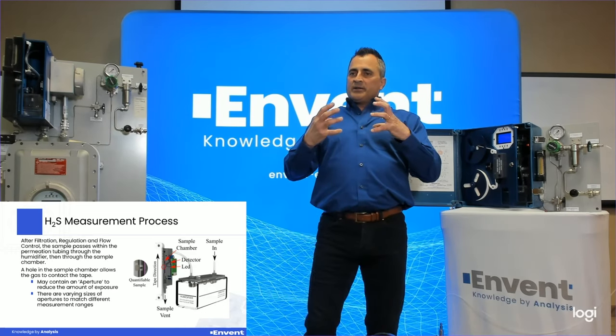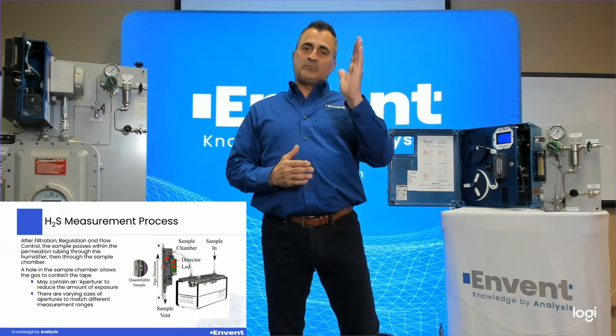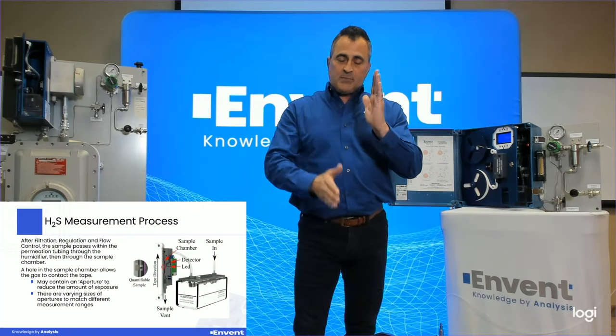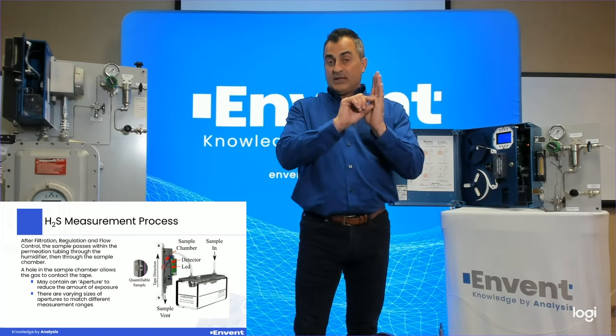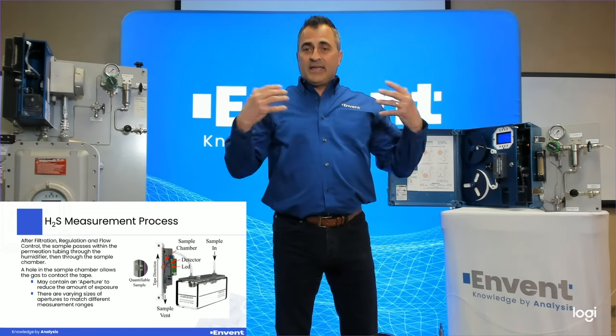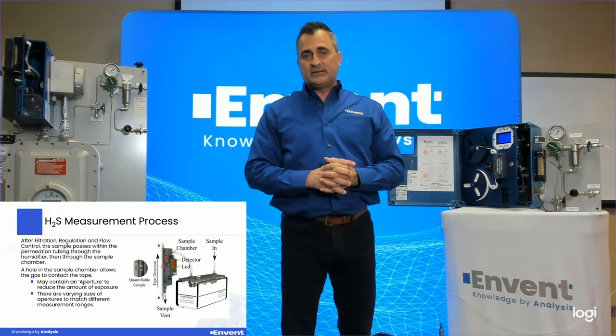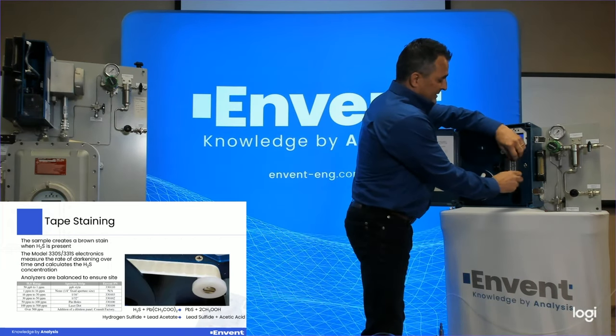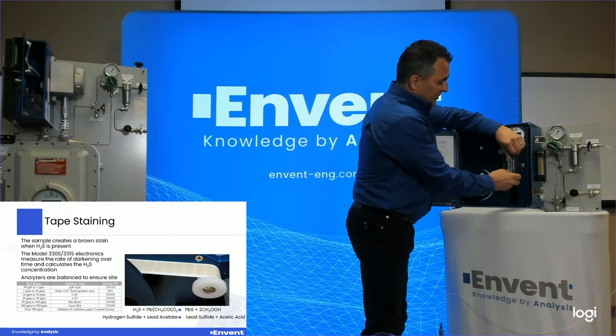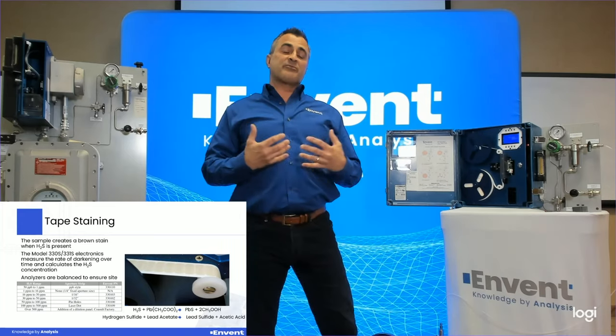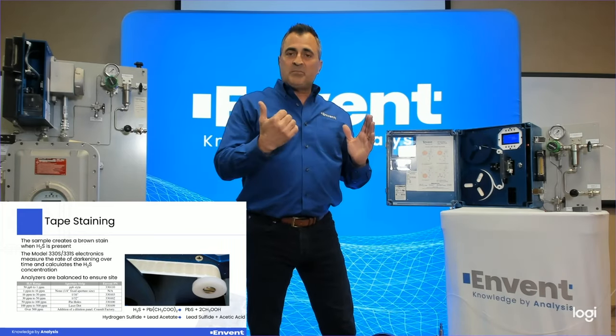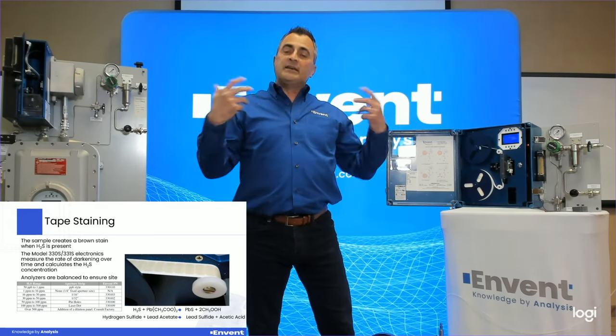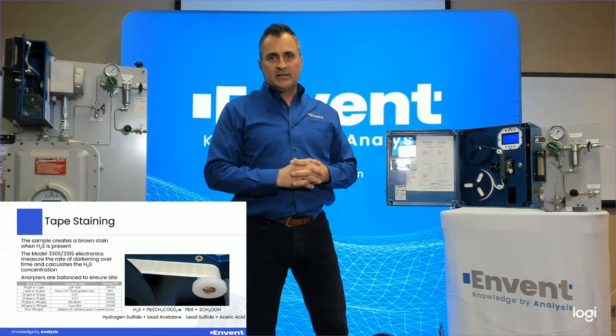We go through the humidifier via a permeation tube, then enter the sample chamber. In the sample chamber we are monitoring the stain. A lot of folks think the tape is constantly in motion — it is not. It's only in motion between analyses: the tape advances and stops. Our sample flow goes past the tape through our aperture and stains it in a small area. The analyzer looks for the rate of change — how quickly is the tape turning brown. The sensor mounted on the sample chamber has an LED that shines light on the tape, and a detector that picks up the amount of reflected light. White tape reflects maximum light; a dark stain reflects less, and that's how H2S concentration is calculated.